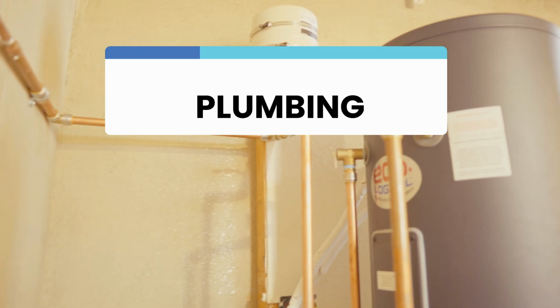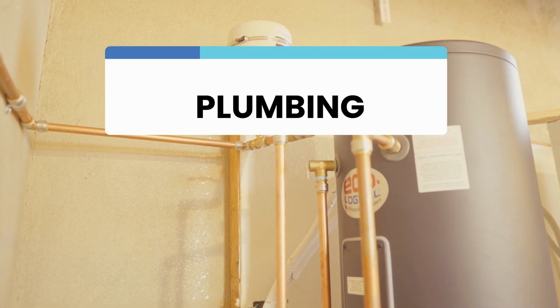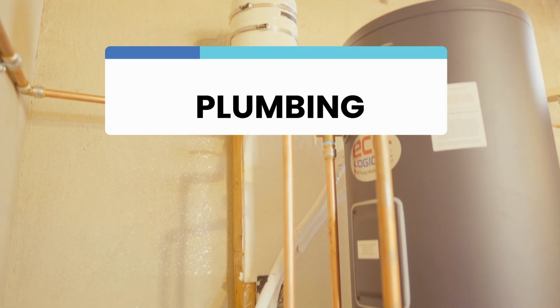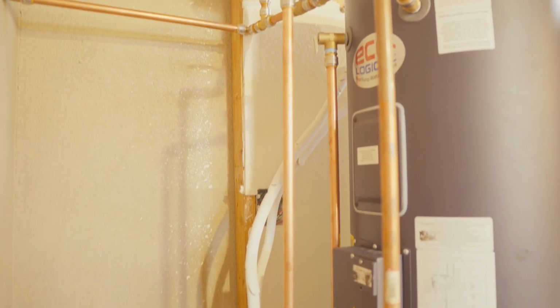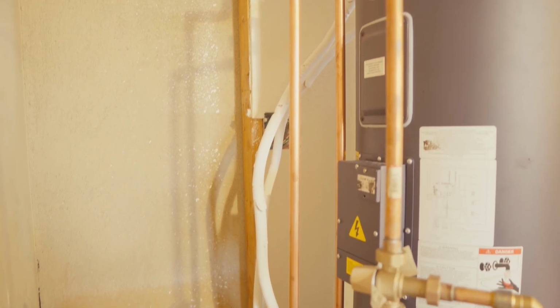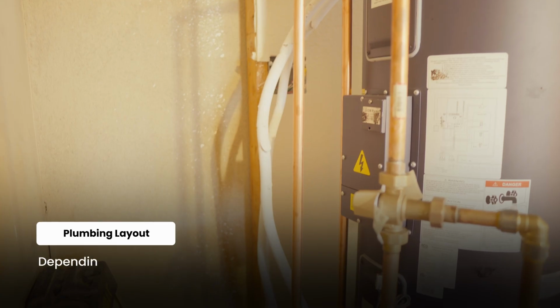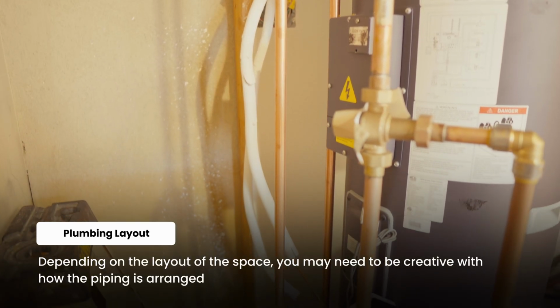Now it's time to install the plumbing that supplies water to the heat pump water heater. The main objective in this step is to route cold water from the source to the unit's cold water inlet. Depending on the layout of the space, you may need to be creative with how the piping is arranged.